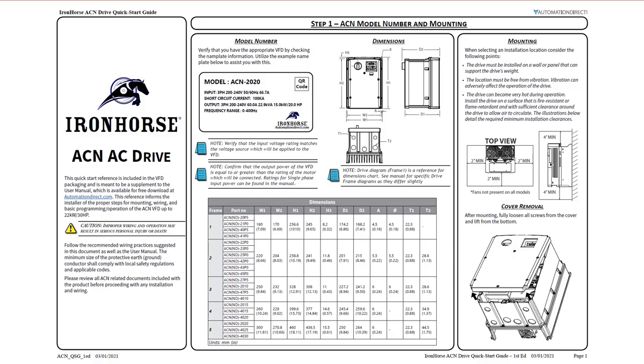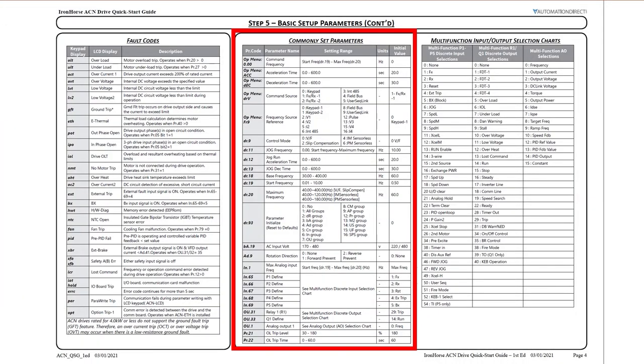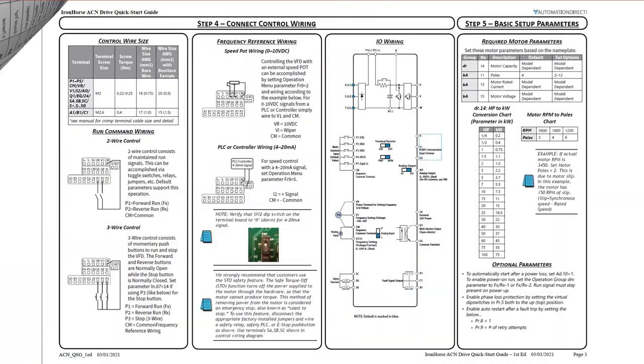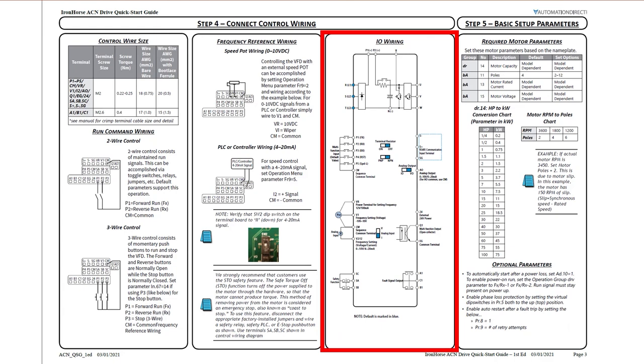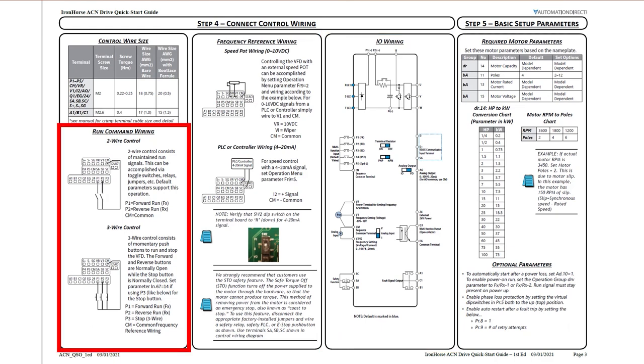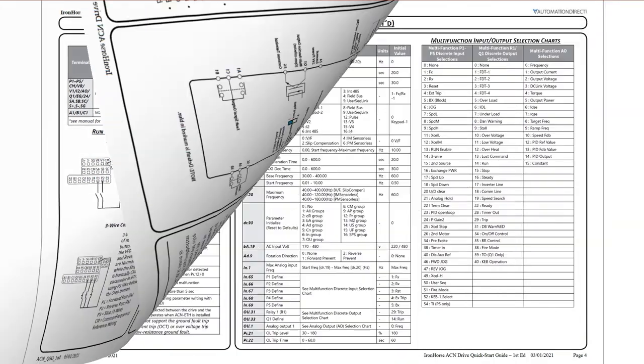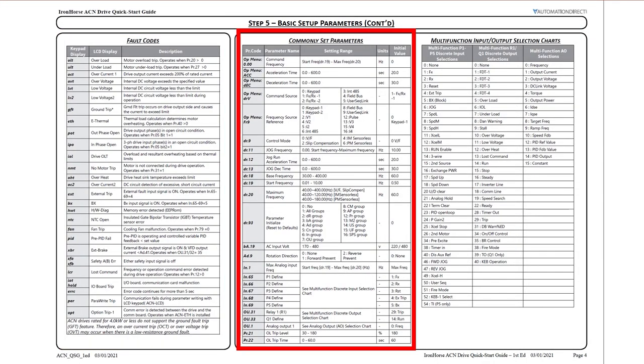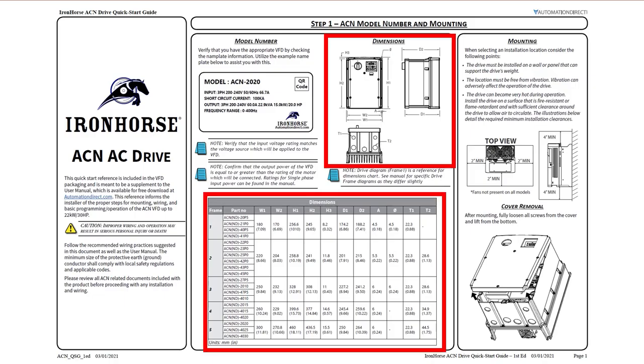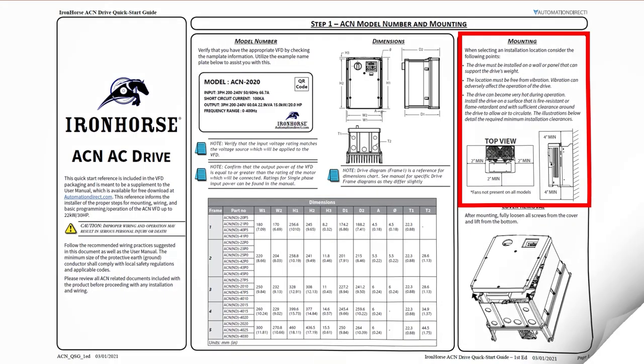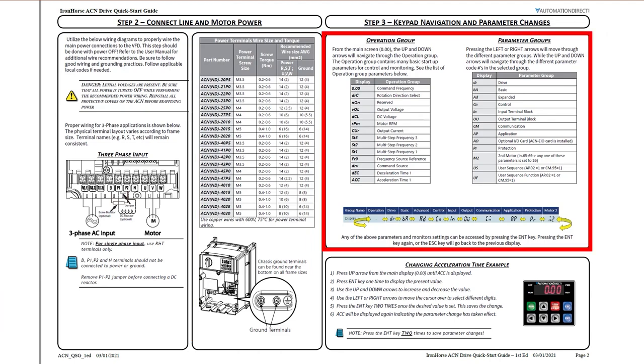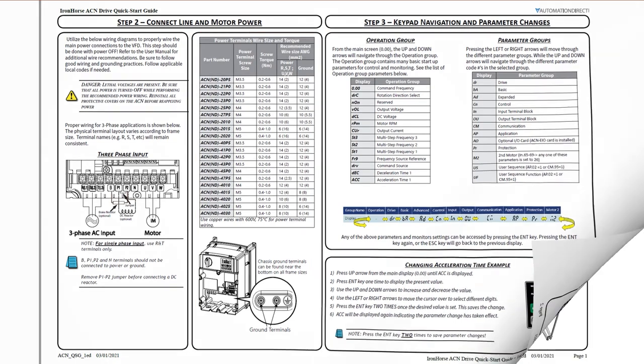And the product insert has a lot of really useful stuff like where to find basic motor parameters, a horsepower to kilowatt converter, a quick wiring diagram, how to use external switches for command control and a potentiometer for frequency control, a list of fault codes, commonly used commands, IO pin assignments, dimensions, mounting, power wire sizes and screw torques, and a list of all of the parameter groups. So keep that guy handy. And if you do misplace it, you can always download a free copy of it or any Iron Horse documentation including 3D models at AutomationDirect.com for free.